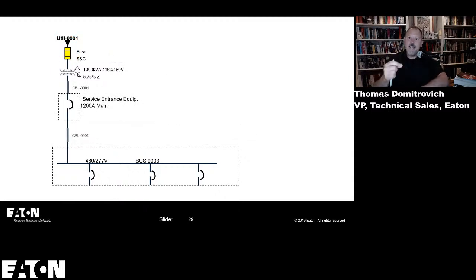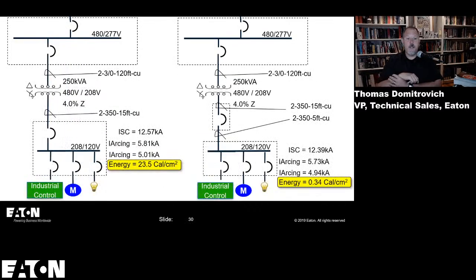Now, a design principle to reduce the incident energy in this panel board, which would be the most common area where an electrical worker would do justified energized work, is to pop that main out of that panel board and basically relocate the energy into this enclosure. There would be much less likelihood of having to open that box than getting into the main panel board on the secondary of that transformer, whether it's your service entrance equipment or downstream somewhere in your power distribution system. Now, what does just moving this overcurrent device out of that panel board do for the electrical worker from a safety perspective? I'm going to show you.